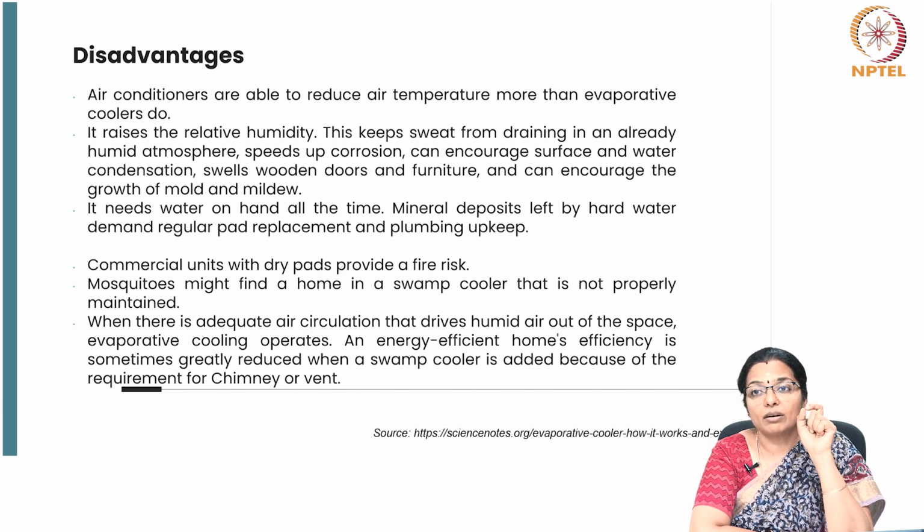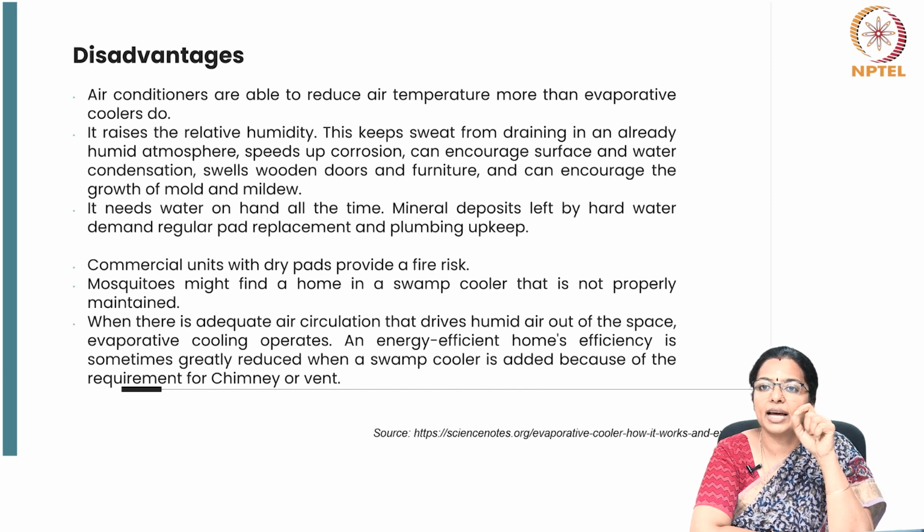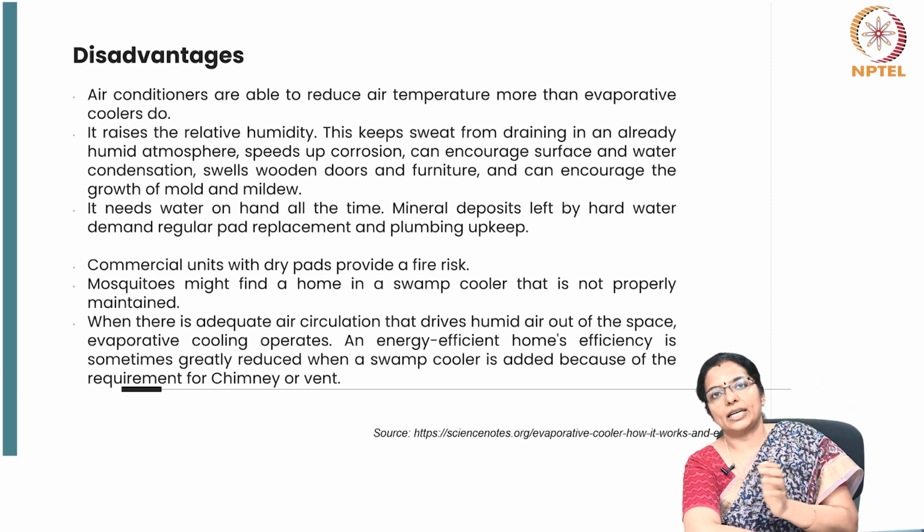Mosquitoes can become a huge nuisance if the home has a cooler which is not properly maintained. Evaporative cooling operates when there is adequate air circulation that drives humid air out of the space. And energy efficient homes' efficiency is sometimes greatly reduced when a swamp cooler is added because of the requirement of a chimney or a vent.